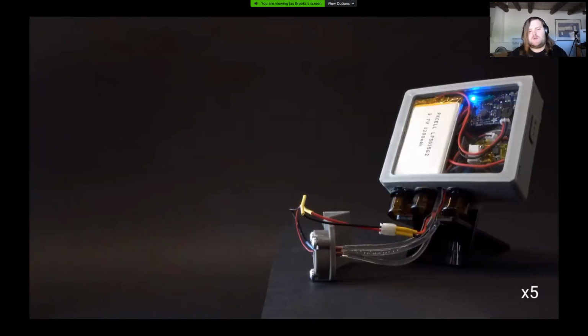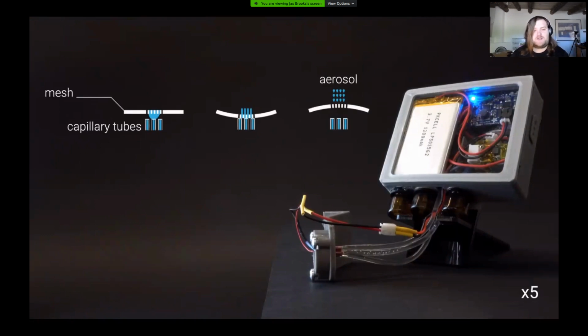Now, when we're designing the device itself, we had to address 2 specific problems that were going to arise. The first was that capsaicin doesn't evaporate at the same temperature as alcohol. In fact, it needs a really high temperature for that to happen. So we couldn't use something like evaporation to actually deliver the compound. Instead, we have to keep everything in liquid phase. To do that, we use something called a vibrating mesh transducer, which has a bunch of tiny holes, and that creates an aerosol of fine, tiny droplets. That means that we can atomize suspensions or keep everything liquid phase until it gets to the nose as it is. So capsaicin was able to be atomized.